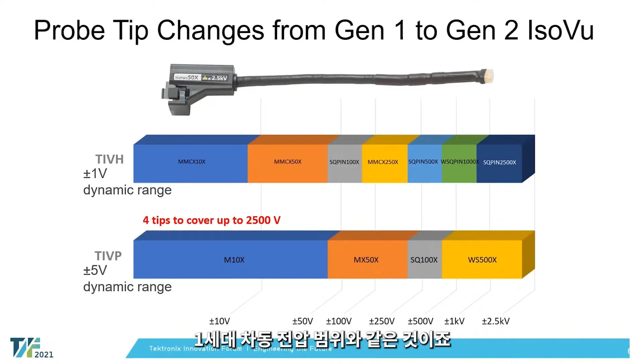And on the second generation probe, the TIVP family, we've extended the bare dynamic range of the probe head itself. So now the probe head, or the SMA connection into the probe tip, into the probe head itself, is now plus or minus 5 volts. And what that allows us to do is actually reduce the amount of attenuation required to get all the way out to 2.5 kV. So you'll see for the Generation 2, we now only have 4 different tips available that cover, again, that same differential voltage range as Gen 1.